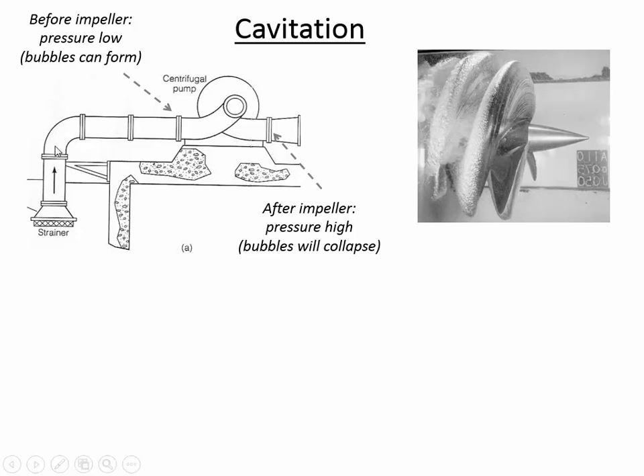But then as we move through the pipe, the pressure is getting more and more negative. As we go up, the pressure is becoming negative very quickly because we're changing elevation. But even as we move horizontally, the pressure is still decreasing because of pipe friction. And so anything that promotes a lot of pipe friction is going to cause this risk of the pressure getting really low. And remember, last semester in fluid mechanics, we talked about how there's two ways to boil water. You can either boil water by increasing the heat, and then it boils because the vapor pressure exceeds atmospheric pressure.